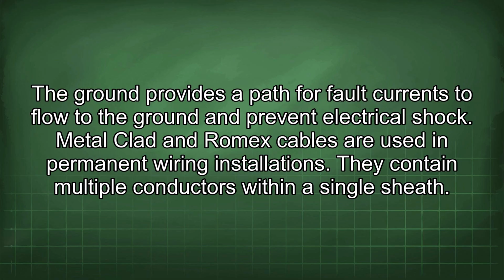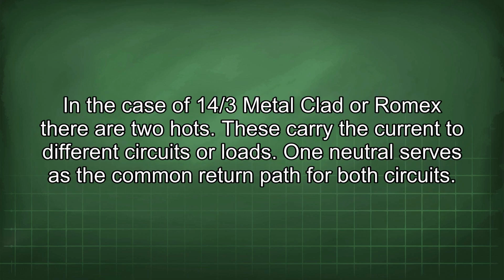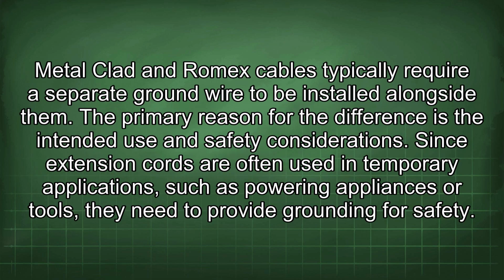Metal-clad and Romex cables are used in permanent wiring installations. They contain multiple conductors within a single sheath. In the case of 14/3 metal-clad or Romex, there are two hots. These carry the current to different circuits or loads. One neutral serves as the common return path for both circuits. Metal-clad and Romex cables typically require a separate ground wire to be installed alongside them.